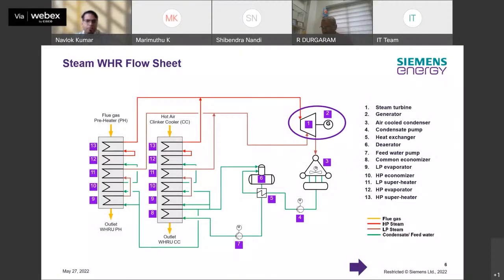Coming to the waste heat recovery boilers, a lot of improvement has been made in its design to improve its uptime. As rightly said by Durgaram sir, the biggest challenge in these components when it comes to waste recovery is the dust that they handle. So a lot of improvement has been made in its design to improve the boiler uptime, its response to varying load conditions, and most importantly, to offer the best thermal and process design with same available waste heat.